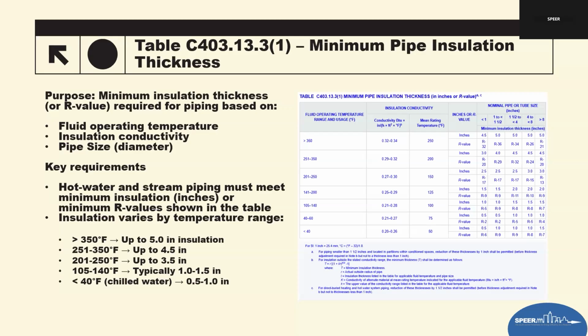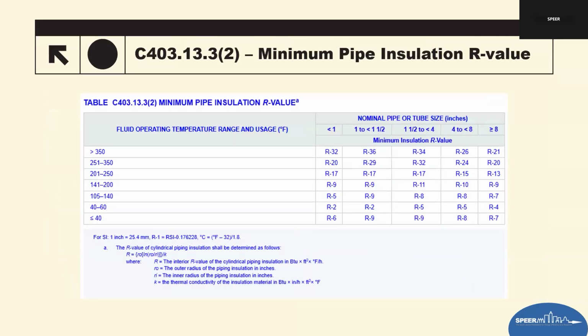Plan review tip: verify insulation thickness or R value matches the table for correct fluid temperatures. Confirm insulation conductivity matches tested values or adjust using the code formula. Check whether any adjustment notes apply, such as small pipe or buried piping, which allow reduction of the thickness of insulation, but never less than 1 inch. And then field inspection: measure insulation on site, especially large diameter hot water piping. Ensure insulation is continuous, properly sealed, and installed without compression. And then watch for uninsulated fittings such as elbows, valves, flanges. Those must be insulated to the equivalent performance or R value or thickness required depending on temperature and pipe size.